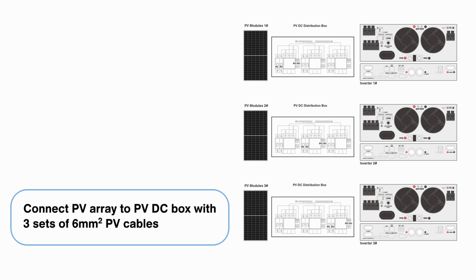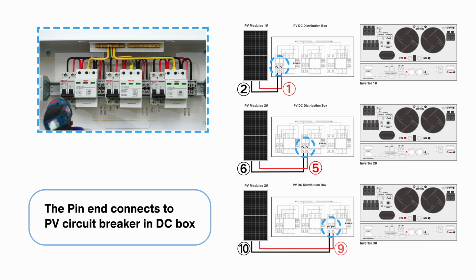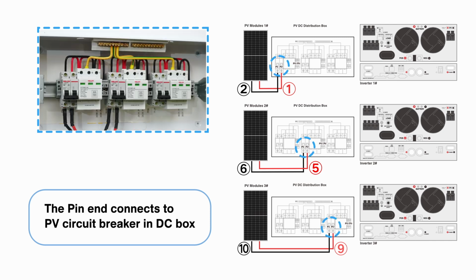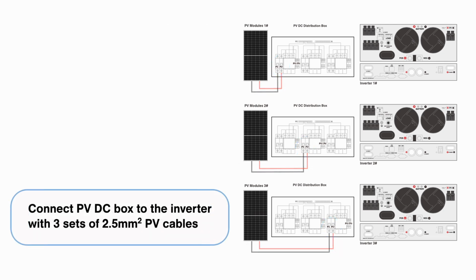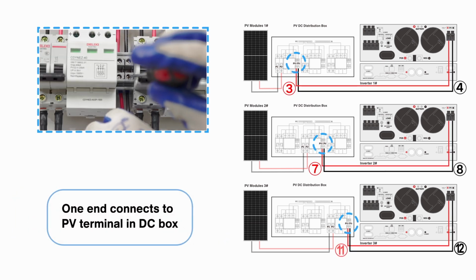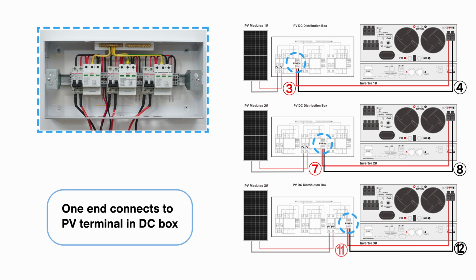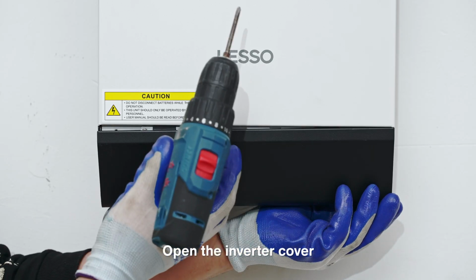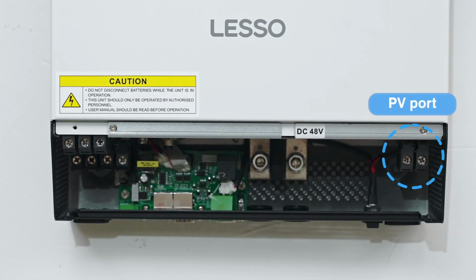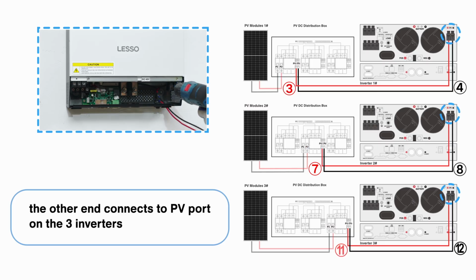PV cable connection. Connect PV array to PV DC box with 3 sets of 6 mm squared PV cables. The pin end connects to PV circuit breaker in DC box. Connect PV DC box to the inverter with 3 sets of 2.5 mm squared PV cables. One end connects to PV terminal in DC box. Open the inverter cover. The other end connects to PV port on the 3 inverters.